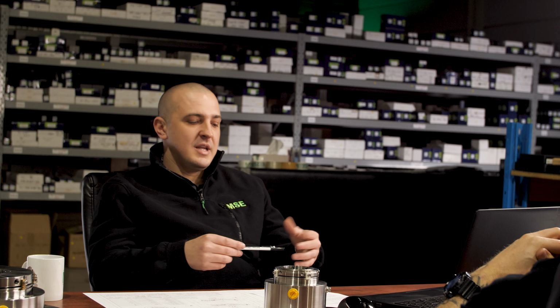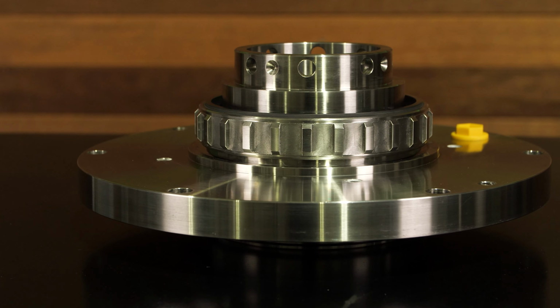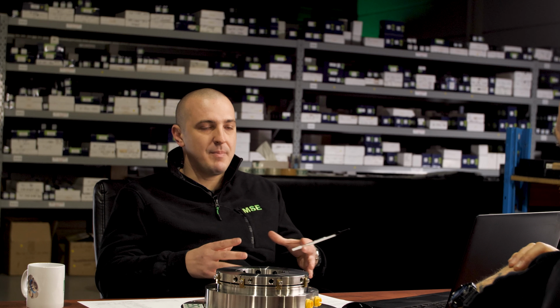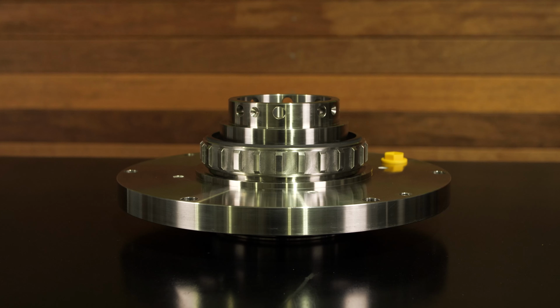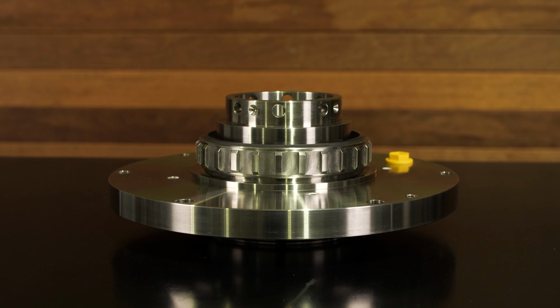How did you address that issue? We needed to increase the flow, so we increased the flow assist in the mechanical seal itself, with a more robust or better designed pumping ring or pumping mechanism within the tandem seal. Along with that, eliminating any 90-degree fittings or smaller diameter fittings that would restrict the flow, as well as using a lower viscosity barrier fluid, which also promotes flow, along with a more robust design altogether.